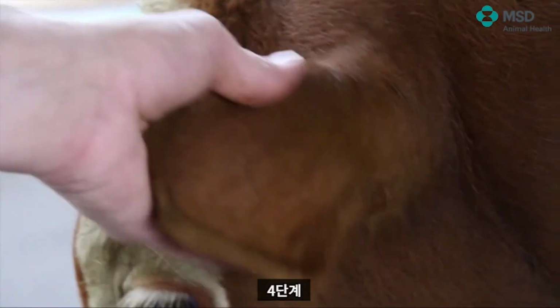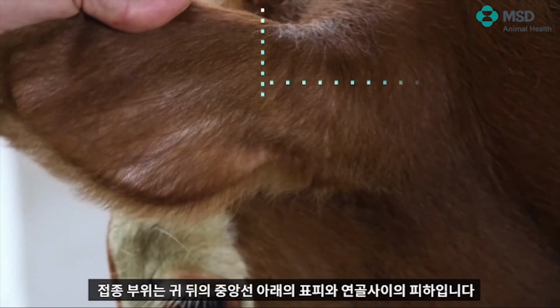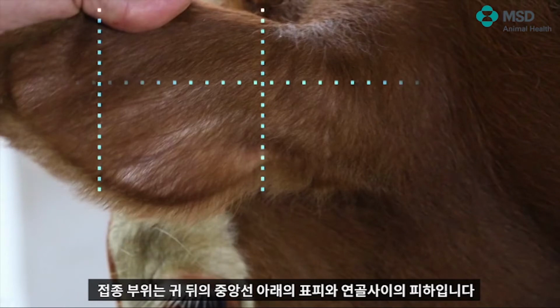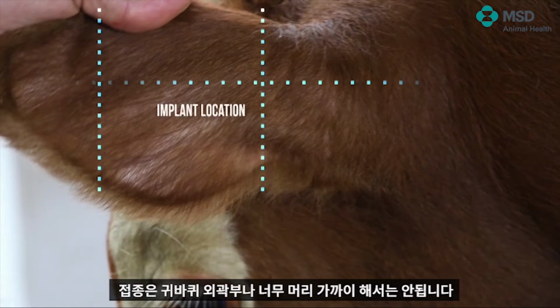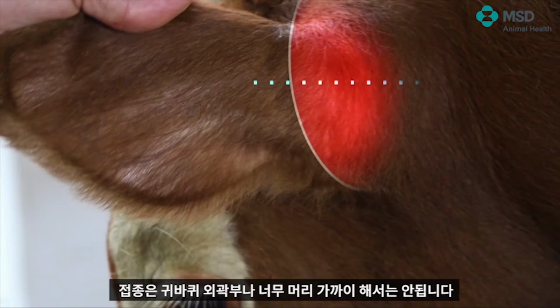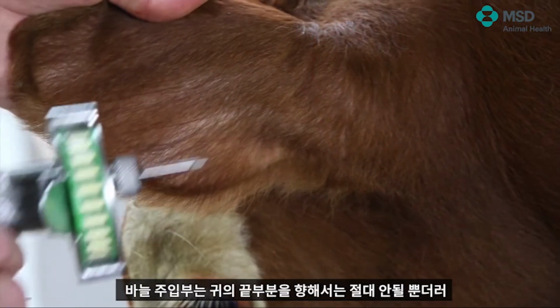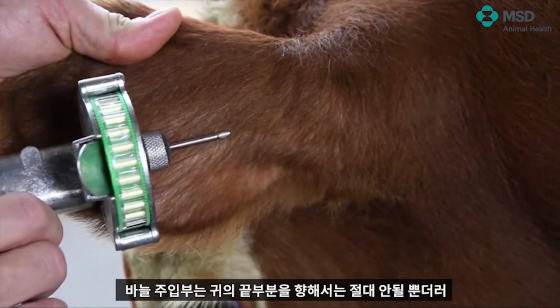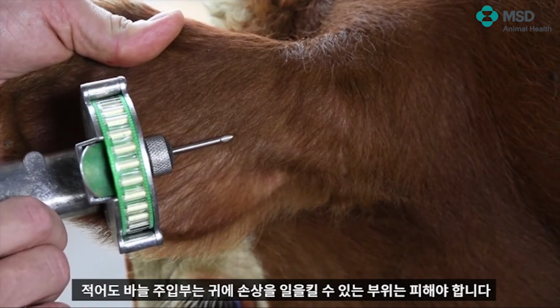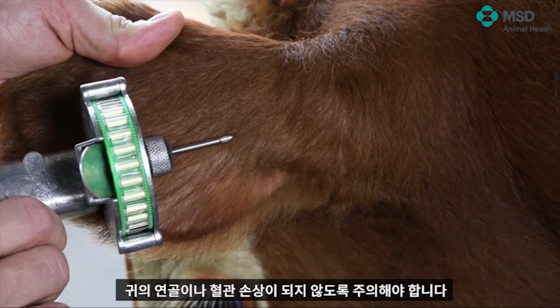Step 4. The implant site is subcutaneous between the skin and cartilage on the back side of the ear and below the midline of the ear. The implant must not be deposited closer to the head than the outer edge of the auricular cartilage ring. The location for the insertion of the needle should be at a point toward the tip of the ear, at least a needle length away from the intended deposition location. Take care to avoid injuring the major blood vessels or cartilage of the ear.